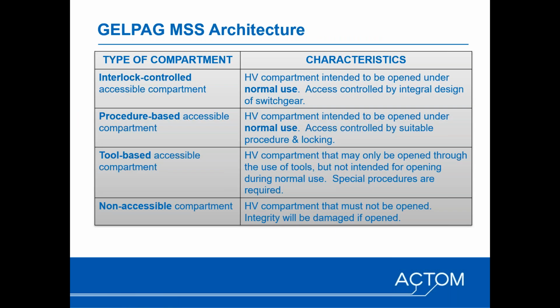So just in terms of the architecture, as I said, going into the details is really beyond the scope of this webinar, but the IEC defines different types of access that can be given to accessible compartments. Obviously, by definition, it doesn't apply to a non-accessible compartment. And typically, if you access a non-accessible compartment, you destroy the integrity of that compartment. For example, the gas would be let out if it's GIS.